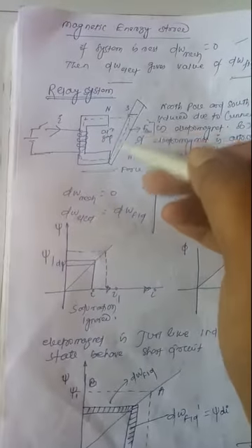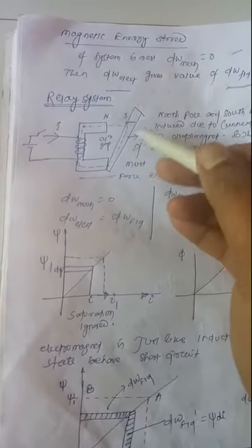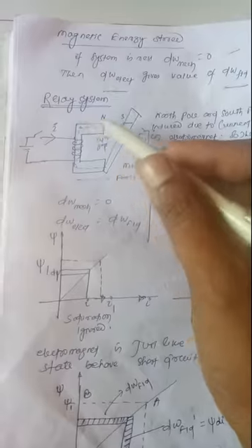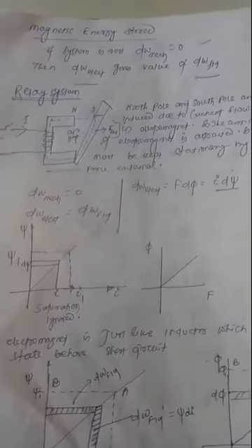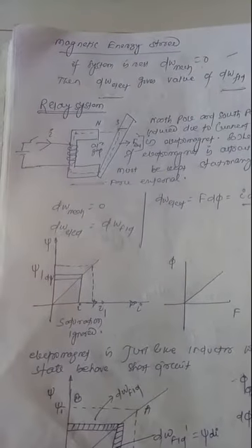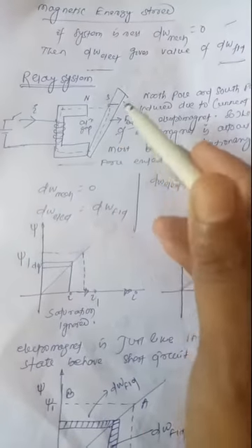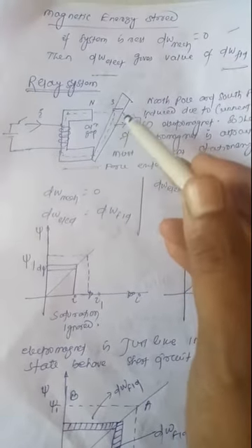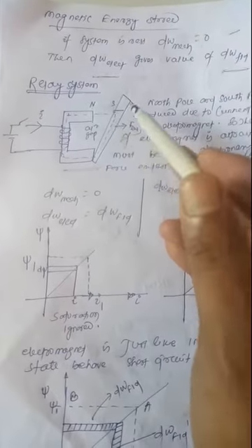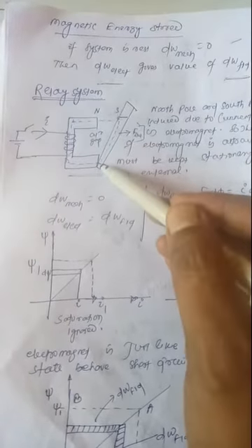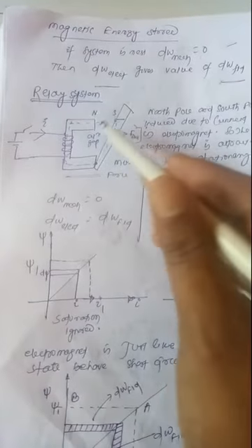So this relay structure is nothing but your attracted armature type. This one is your armature, because it is moving; this moving element is generally termed the armature, and this one is your magnetic system. Just this magnetic system is energized. When this is connected with the source, it takes a current I. So this core gets magnetized and gives an attractive force upon this hinged armature. The armature is hinged at this point, so this will get closed.